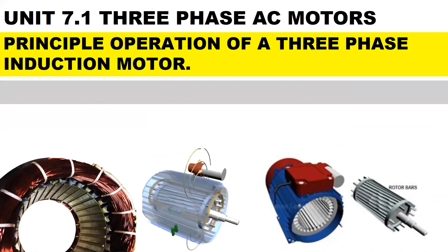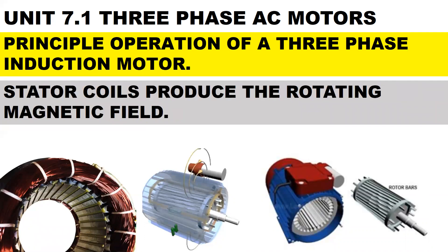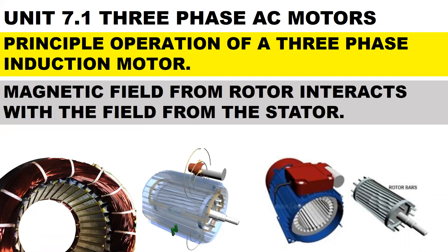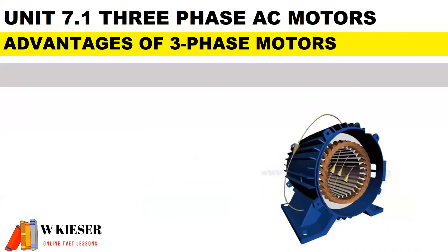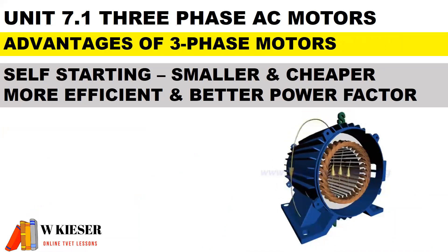In terms of the principal operation of a three-phase induction motor, the supply voltage is applied to the stator coils. The stator coils produce the rotating magnetic field. Then EMF is induced in the rotor, which causes current to flow inside the rotor, and the magnetic field from the rotor interacts with the field from the stator. The biggest advantage of three-phase motors compared to single-phase motors is that they are self-starting, smaller, cheaper, more efficient, and have a better power factor.